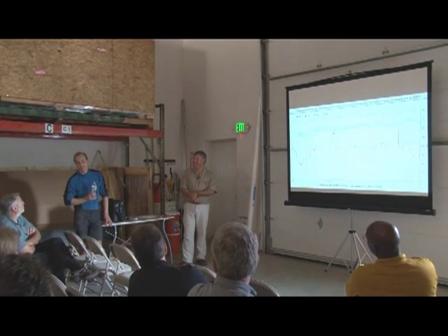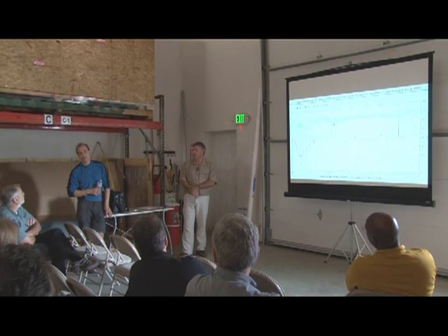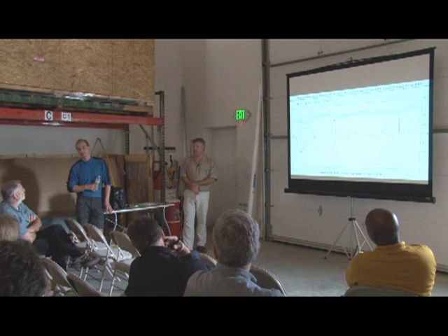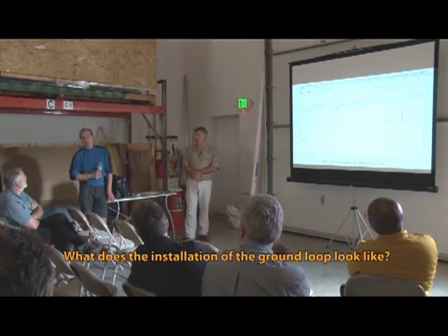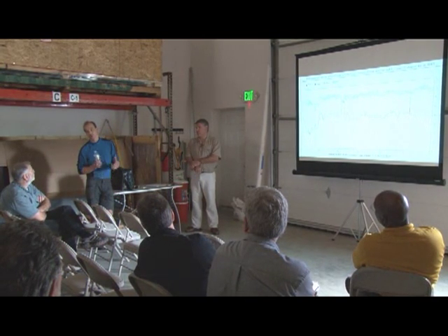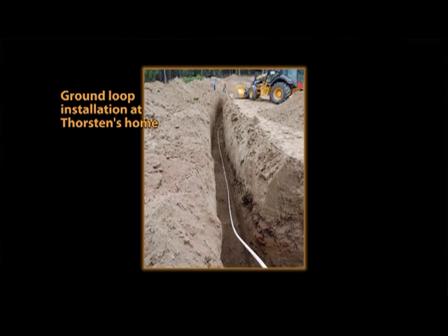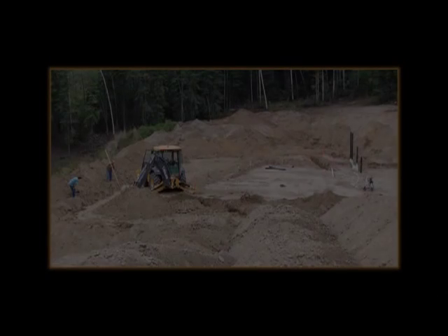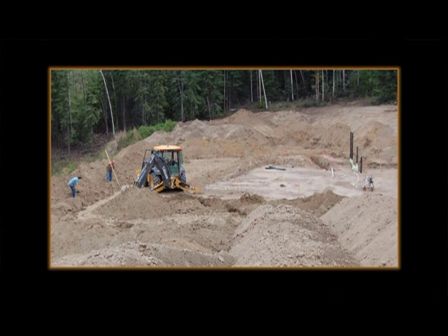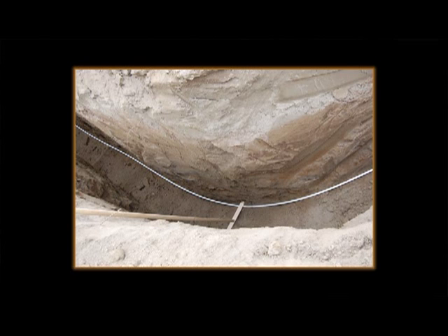On a high-efficient building, you can run your HRV to keep your house from freezing with the ground heat — that's completely a different story than with a normal ventilation system. As for installation: in new construction it's always easier. When we do the septic systems, we're looking for 400 feet of three-quarter inch PEX filled with glycol. We loop it around the house, place it under the septic leach field, then continue a trench, loop it back around and come back into the house. It's a fairly inexpensive installation. In our climate I try to keep it at 10 to 12 feet deep.